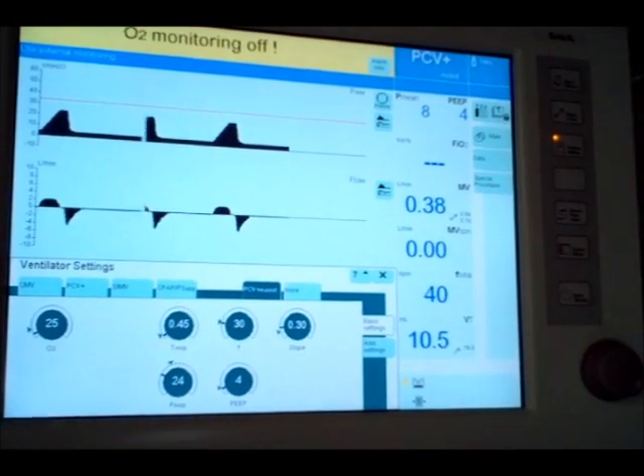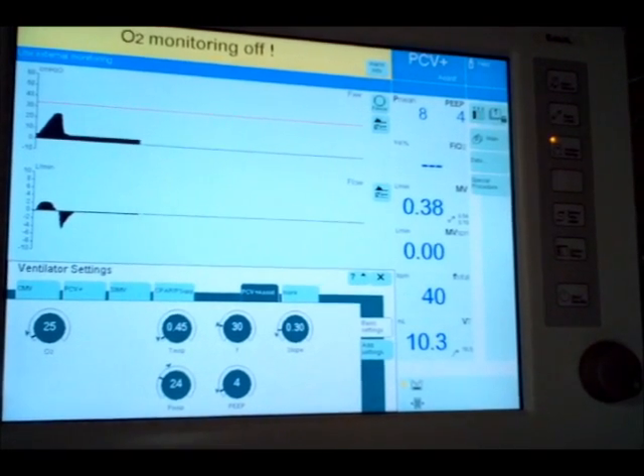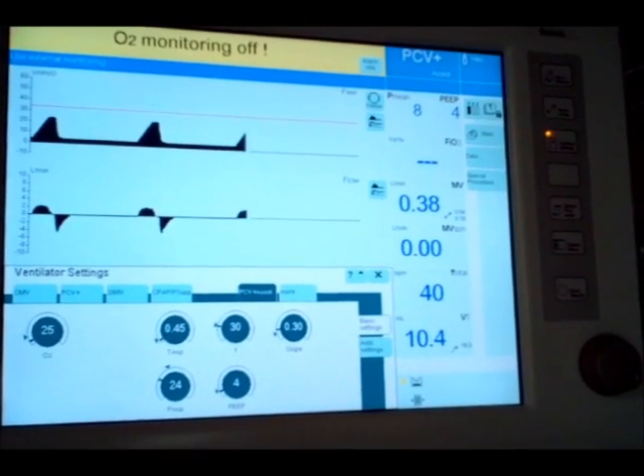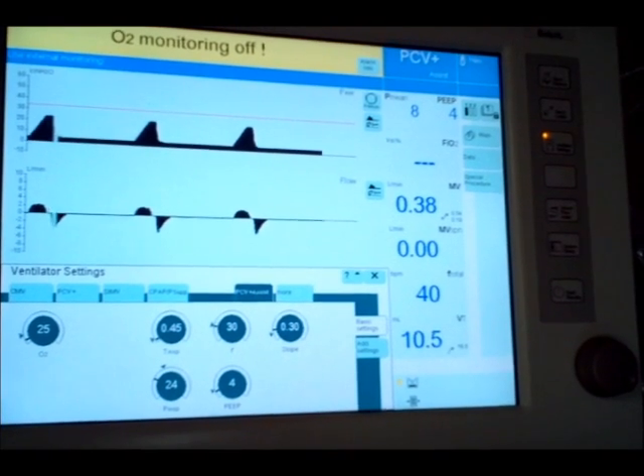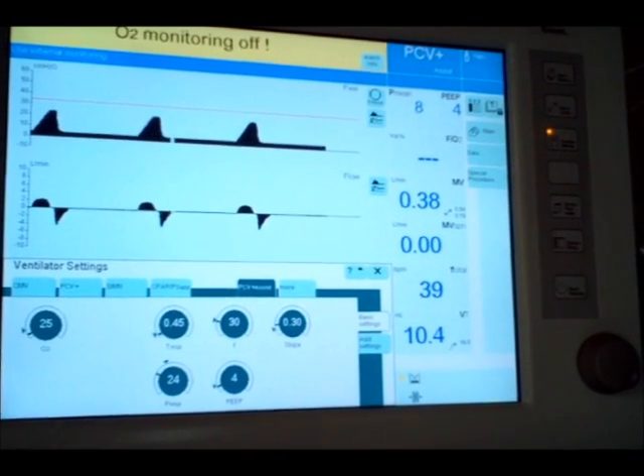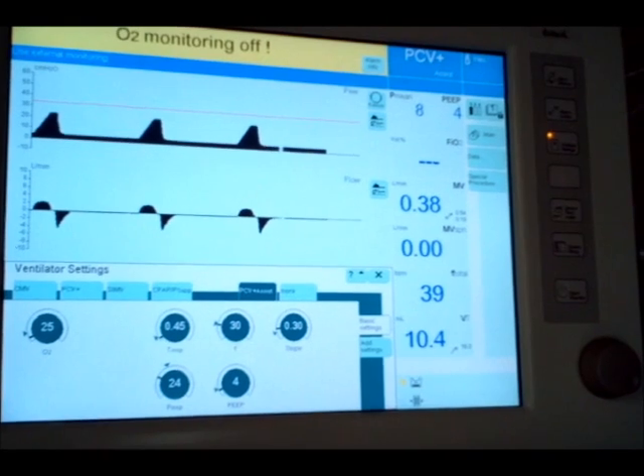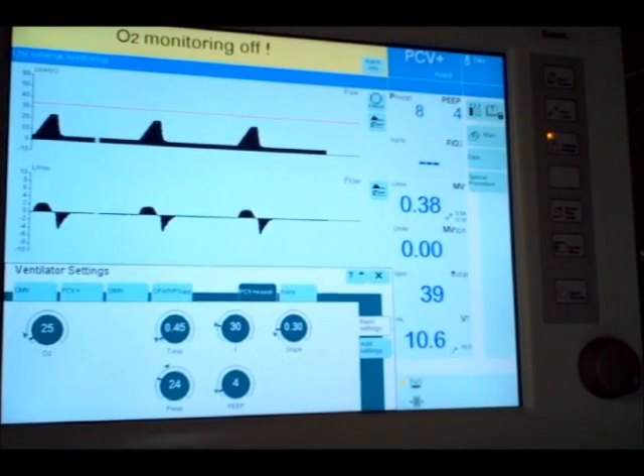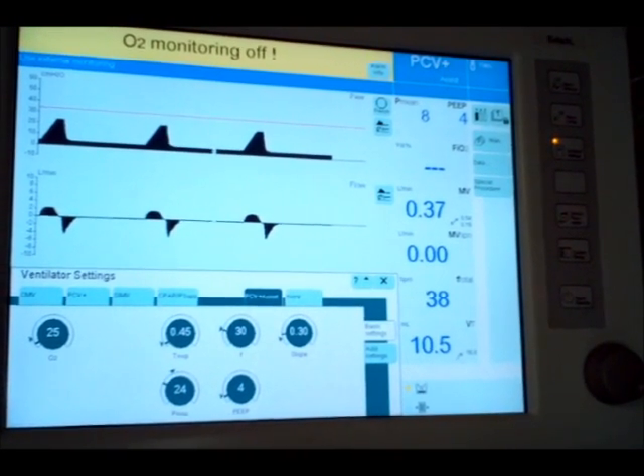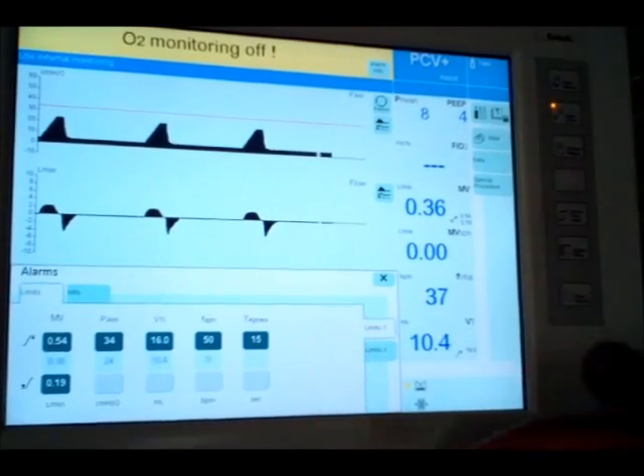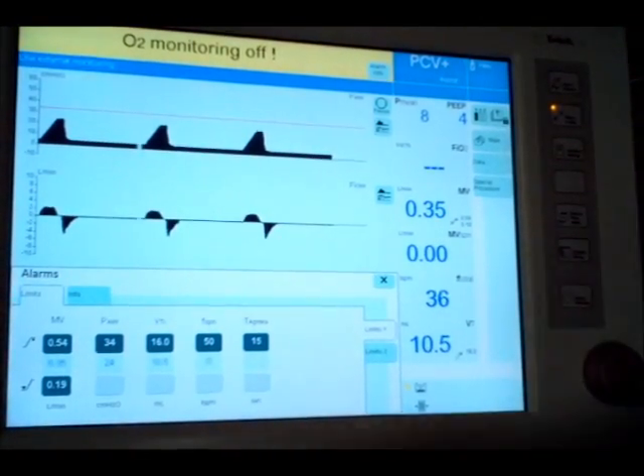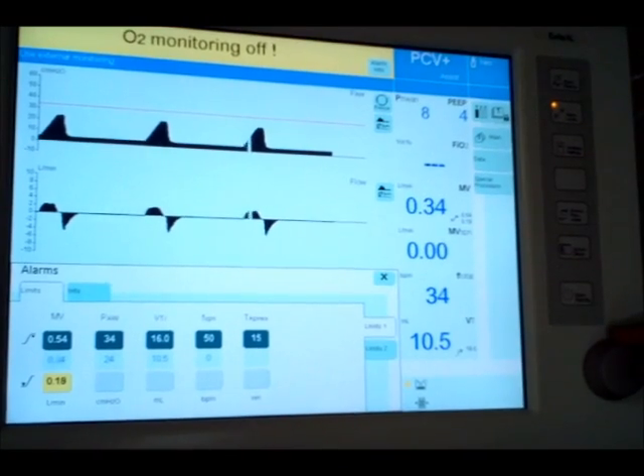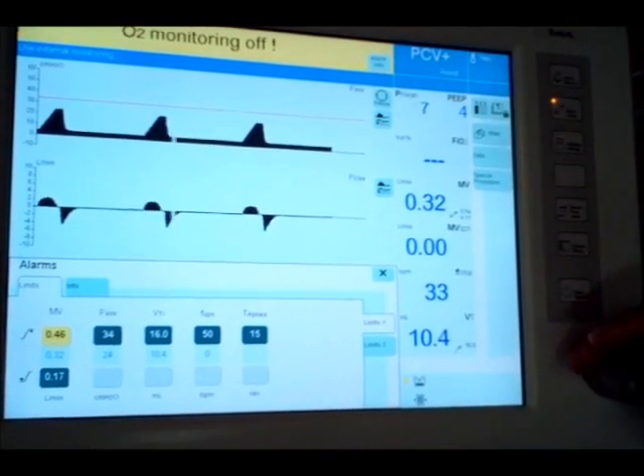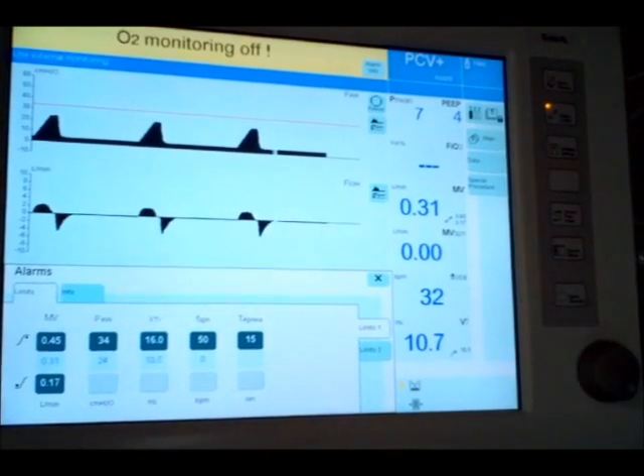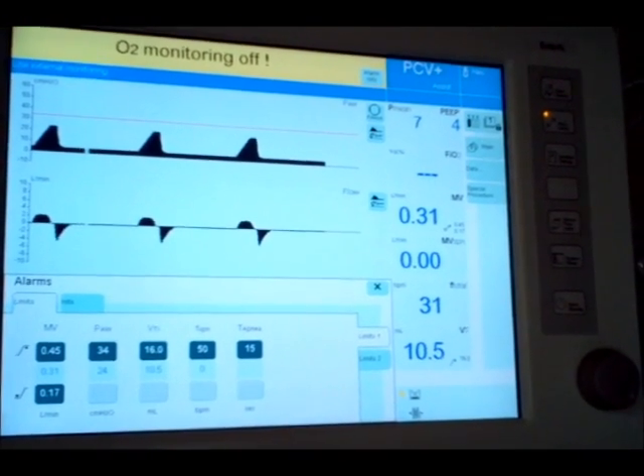You just change the rate. There's no expiratory time to fiddle with to get your rate. Which alarms are going to change if I change the rate? Minute ventilation shouldn't affect my PIP, my peak pressure alarm. It shouldn't affect my high tidal volume alarm. So when you go to your alarm limits, you can maybe save a little bit of time. You turn down the rate, so I'm going to turn down my low minute volume and maybe turn down my high minute volume. Those are the kinds of things I want you thinking about, okay?